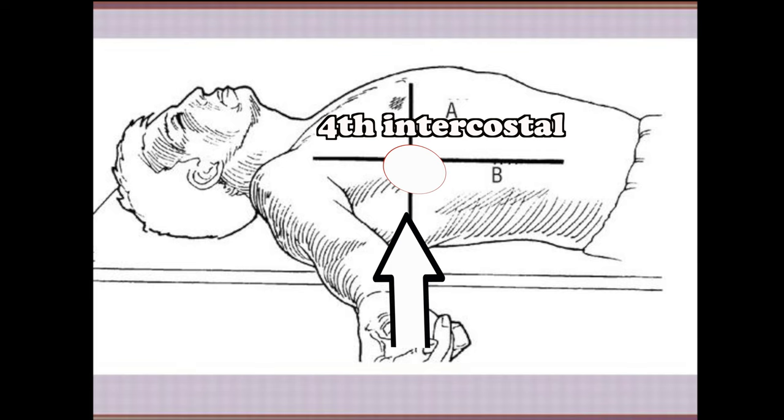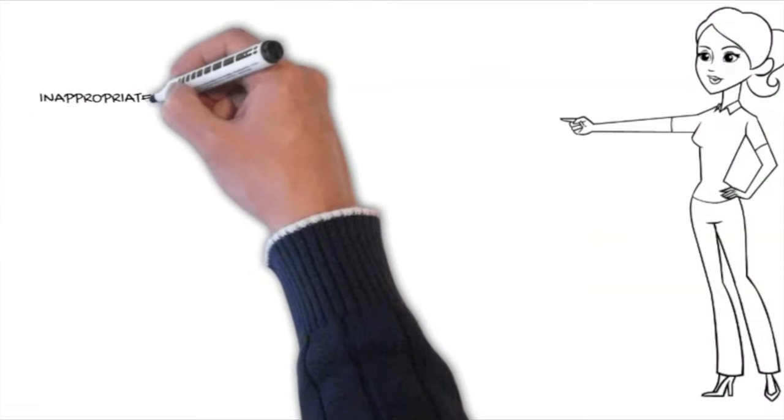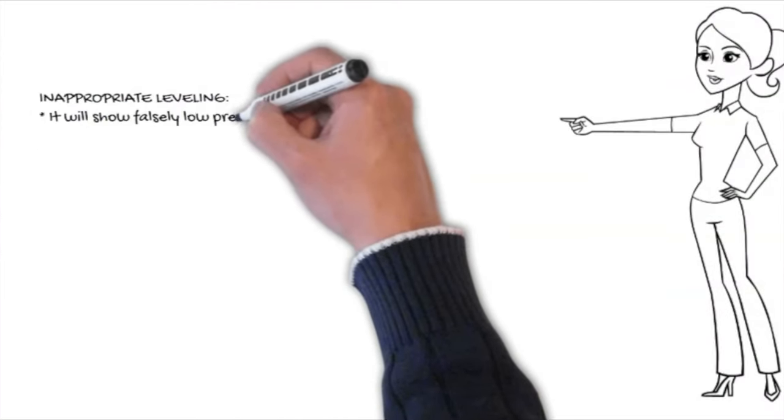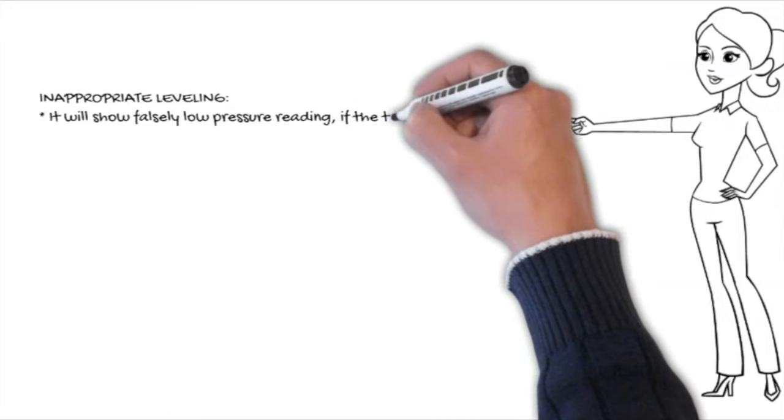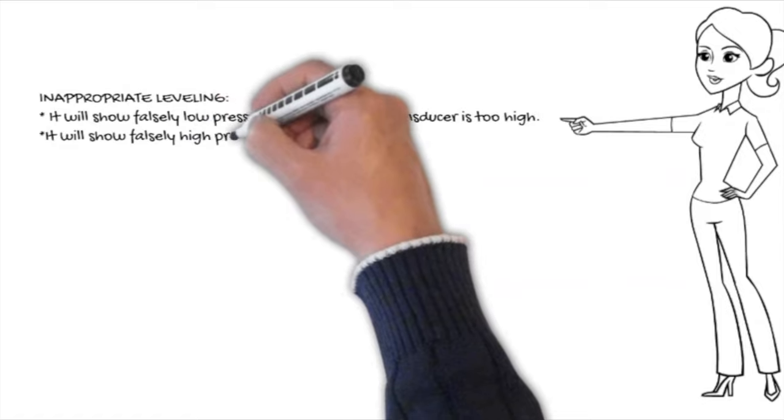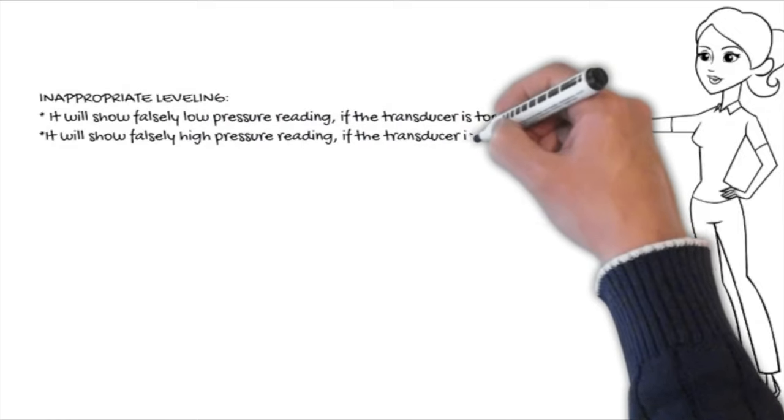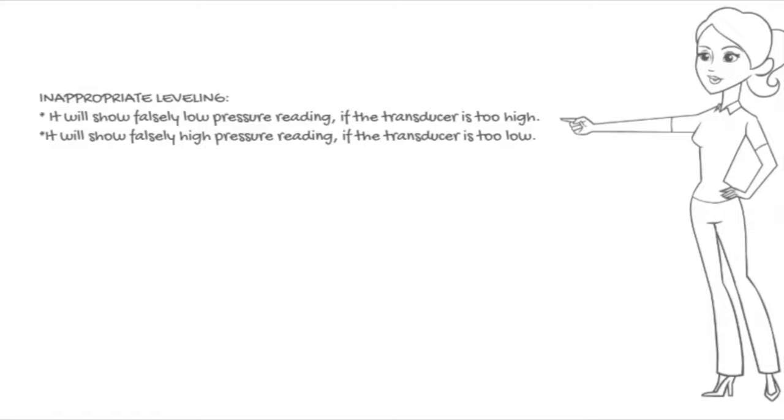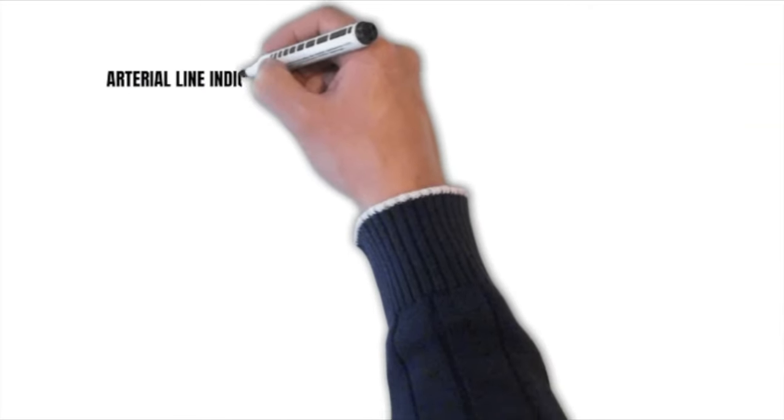If the leveling is inappropriate, it will show falsely low pressure reading if the transducer is too high. It will show falsely high pressure reading if the transducer is too low.